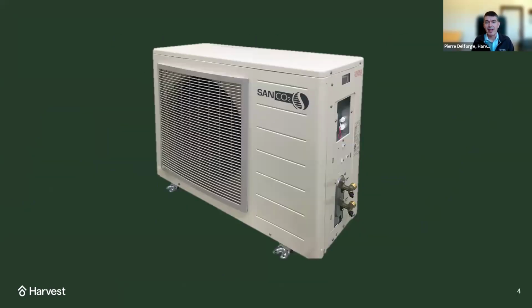So the solution to this 10% emissions problem is heat pumps, of course. They are almost magical in their efficiency, with 300% or more efficiency. And this particular heat pump that I have on the screen here, the Sanco 2, which is a CO2 heat pump, is particularly efficient, with efficiency up to 550% in the best conditions, both because of the CO2 refrigerant and because it's an air-to-water heat pump. It produces 150-degree water, which allows for high storage density, so you don't need a lot of tanks. And typically 1 tank, maybe 2 will be sufficient.